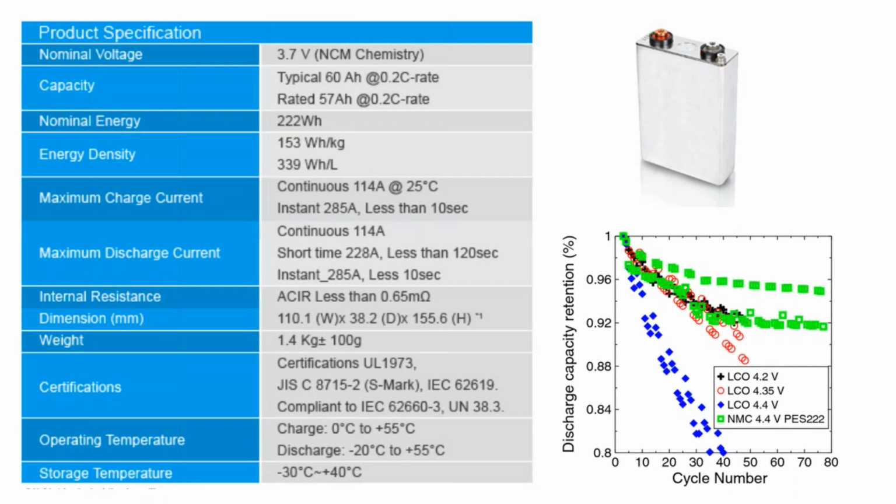And so when you think about it, compared to a lithium iron phosphate that is still a continuous 2-hour battery, versus the lithium NMC, which they're giving you a rating for a continuous half-an-hour battery, you can get away with a smaller battery, substantially less capital expenditure required if your load is particularly spiky.